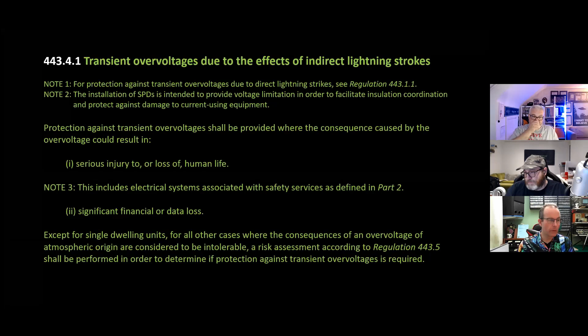There's now also a new part that says significant - this is all new, by the way, that's why it's in green - significant financial or data loss. Then it goes back to the old-fashioned: except for single dwelling units, for all other cases where the consequences of an overvoltage of atmospheric origin are considered to be intolerable, a risk assessment according to Regulation 443.5 shall be performed in order to determine if protection against transient overvoltage is required.